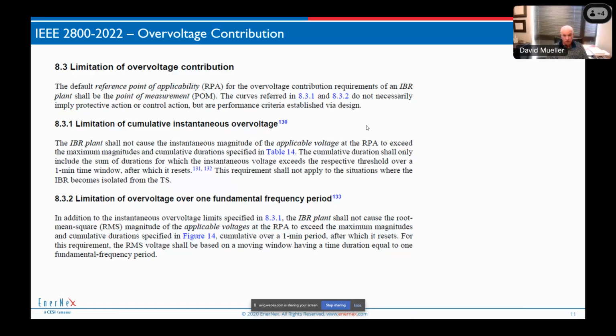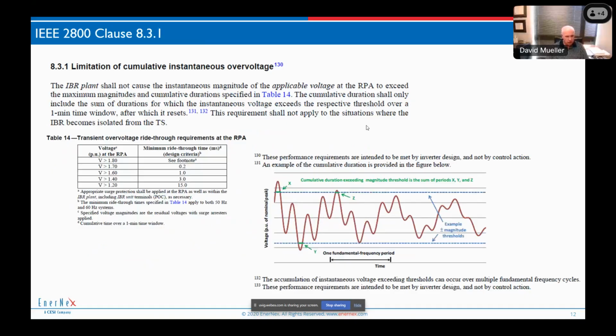My experience is that the inverter equipment manufacturers, if you tell them that they can't produce those overvoltages, that's where they're going to set their trip settings. That's where they're going to set a self-protective overvoltage trip setting, because that's the best way they know to ensure against that. So if we look at the limitation of instantaneous overvoltage, the power quality section says that the plant should not cause instantaneous magnitudes at the RPA to exceed the values in table 14.